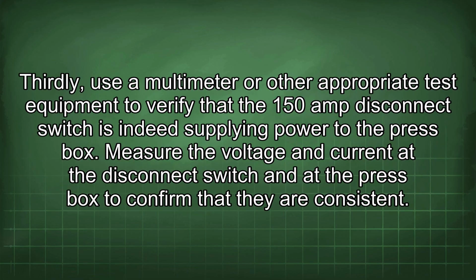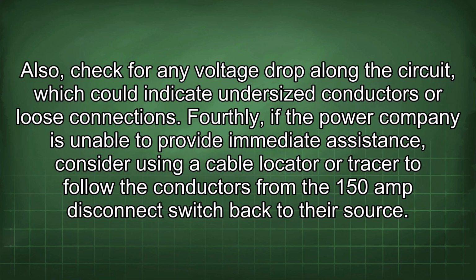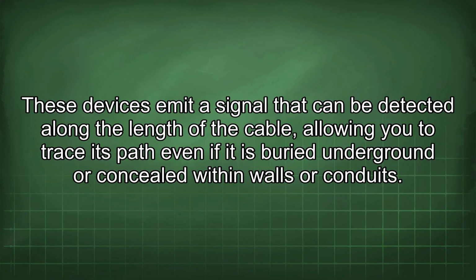Thirdly, use a multimeter or other appropriate test equipment to verify that the 150 amp disconnect switch is indeed supplying power to the press box. Measure the voltage and current at the disconnect switch and at the press box to confirm that they are consistent. Also, check for any voltage drop along the circuit, which could indicate undersized conductors or loose connections. Fourthly, if the power company is unable to provide immediate assistance, consider using a cable locator or tracer to follow the conductors from the 150 amp disconnect switch back to their source. These devices emit a signal that can be detected along the length of the cable, allowing you to trace its path even if it is buried underground or concealed within walls or conduits.